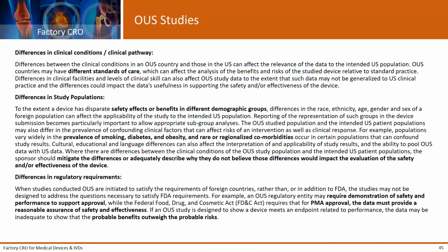You're also going to want to make sure you have a CAPA process in place and a complaint handling process in place, so if there are any problems that occur during the study, you can investigate those complaints and implement corrective actions. You're going to want a reporting procedure, because any adverse events need to be reported. So those are some of the key things that I want clients to focus on when they're doing a clinical study and they're preparing for it.